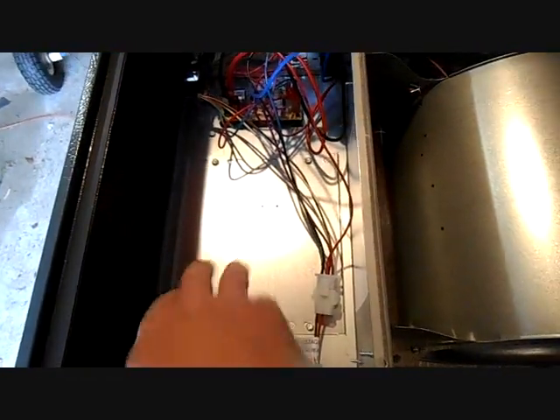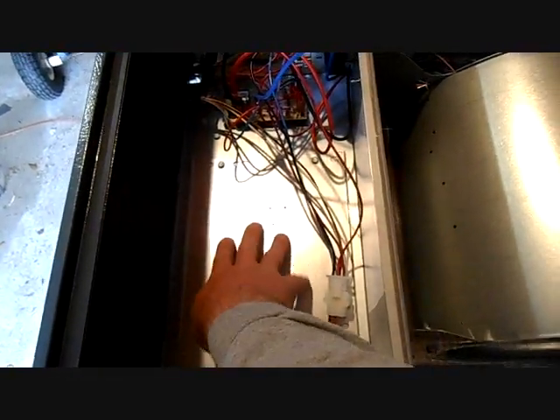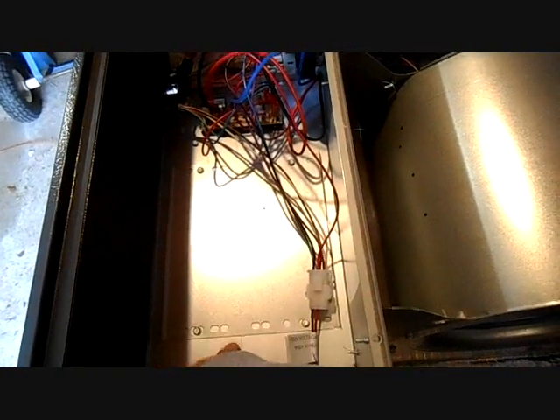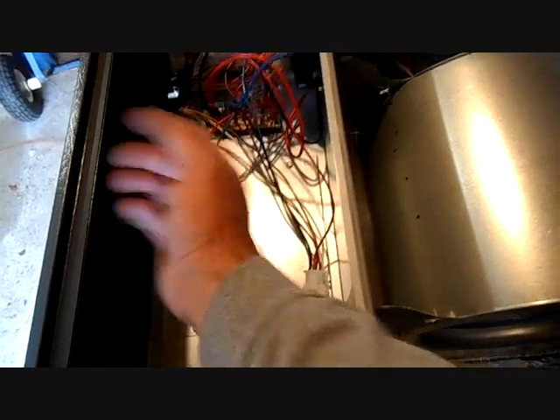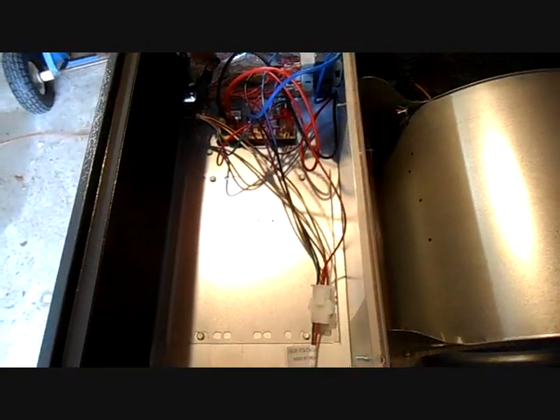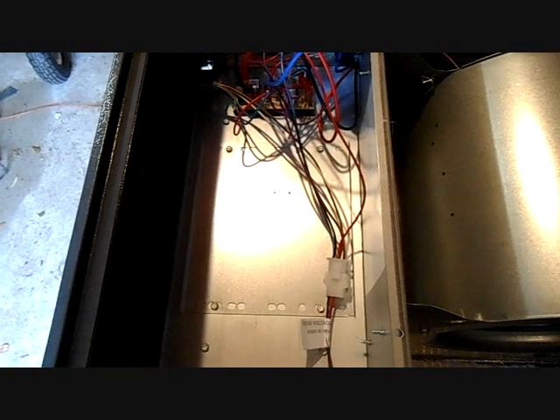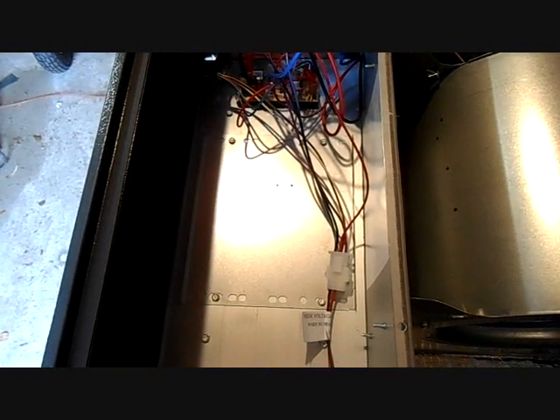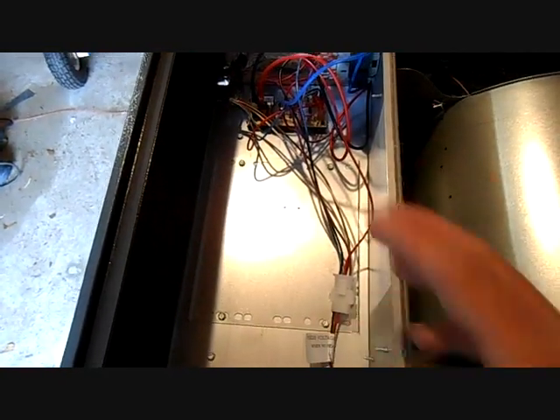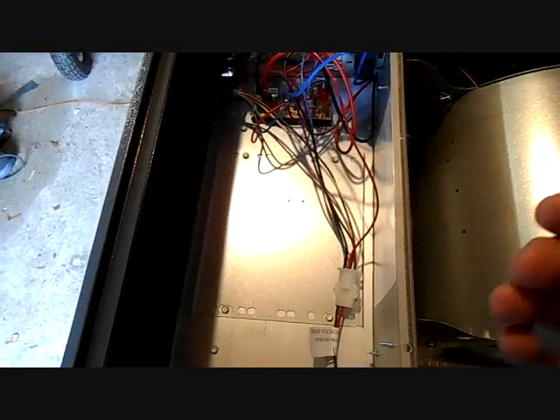And the next thing we'll do is take a look at the heater. On Goodman air handlers, the heater is mounted here. There is a baffle plate you take off. There's four screws. You take it out and slide the heater into it. I will show you how it looks once it is installed. It's pretty simple. It slides right into the opening. You screw it back in the same openings.